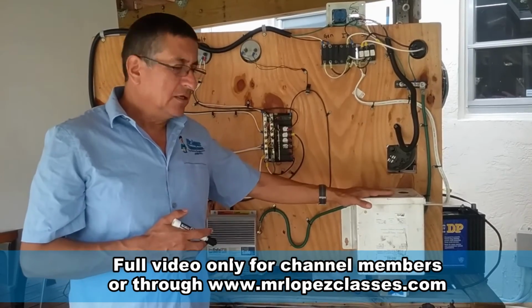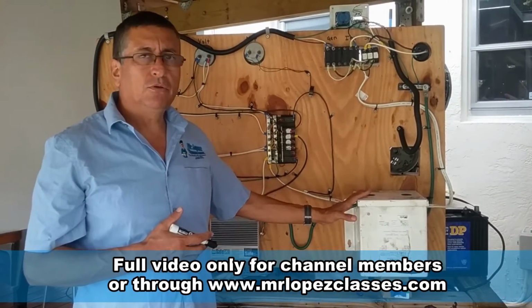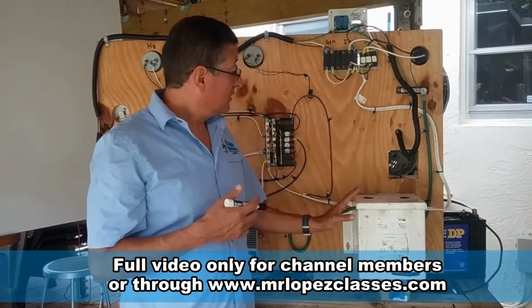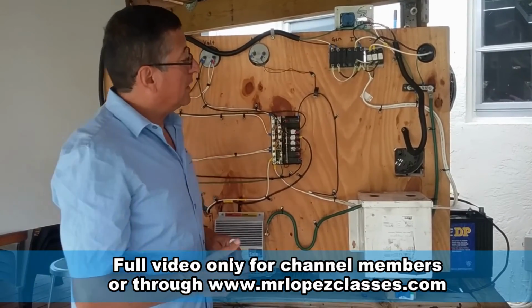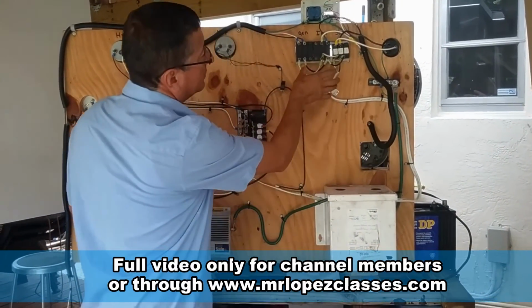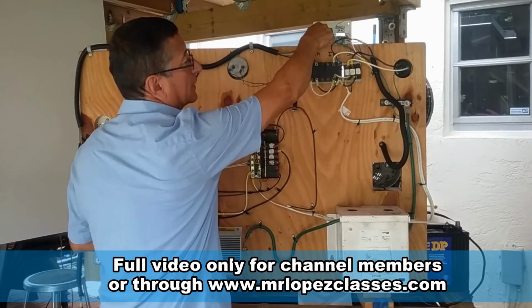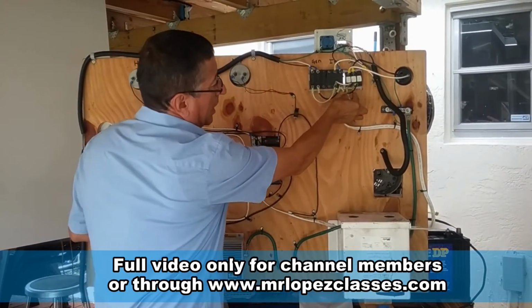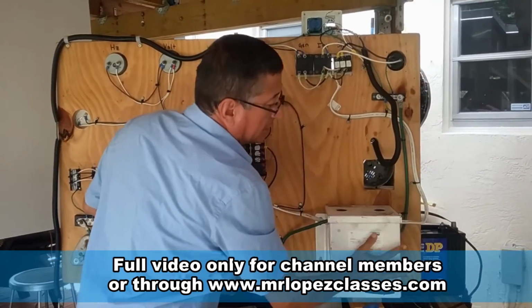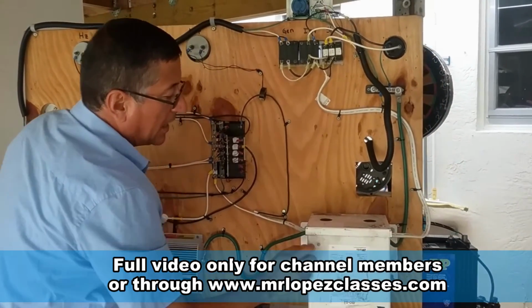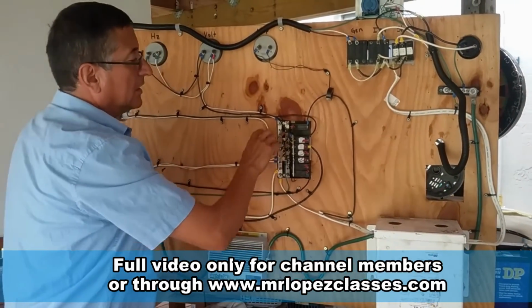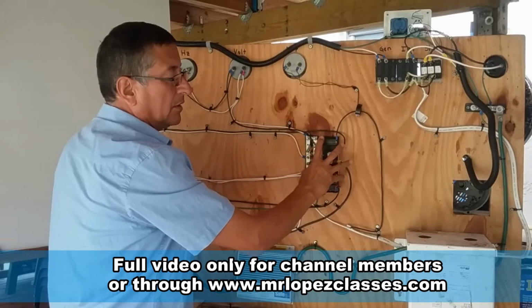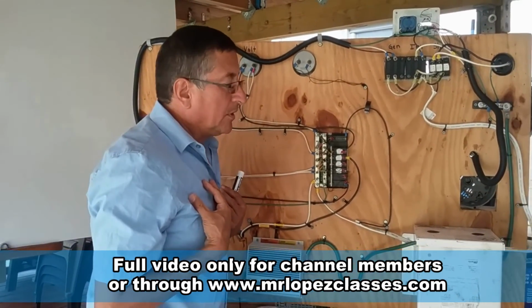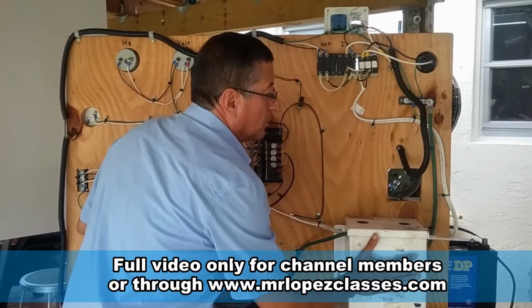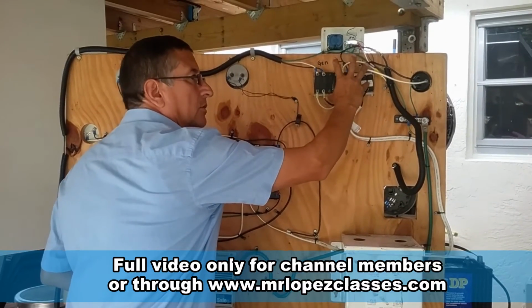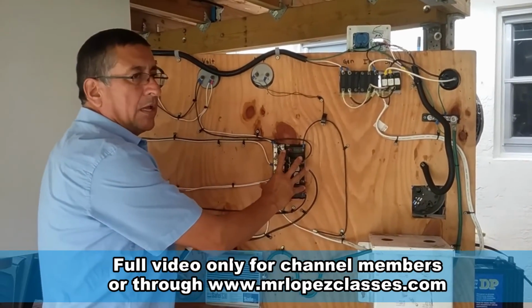Where is the isolator transformer located in a boat? According to my recommendation, the isolator transformer should be located at the output of the switch selector. The power enters the isolator transformer, and then continues and enters the main breaker of the AC panel. According to my recommendation, the isolator transformer should be located between the switch selector and the main panel.